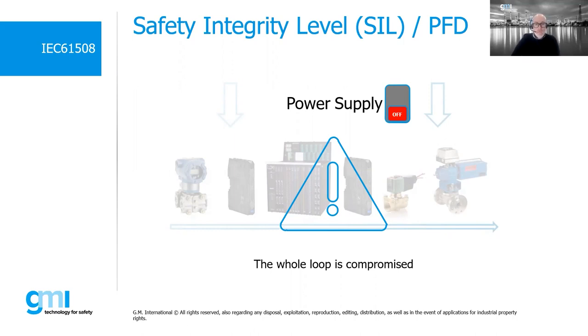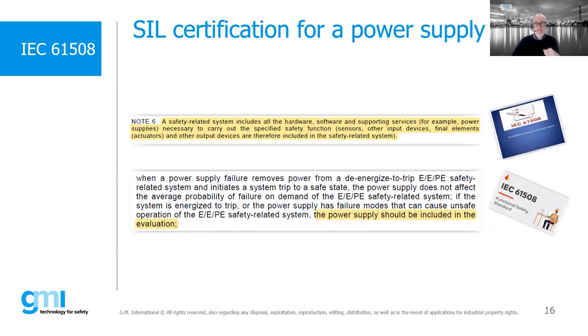In the following slide, some extracts from the IEC 61508 are shown which deal specifically with the power supply system of the SIF, which must be considered in the SIL calculation.